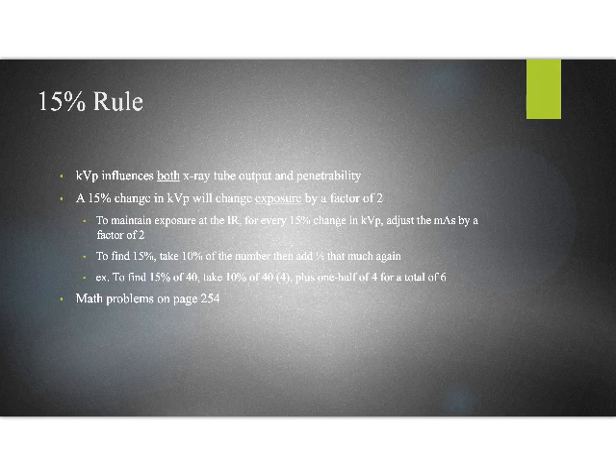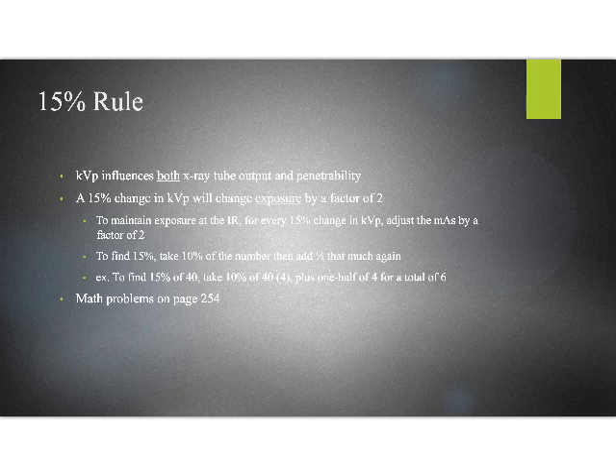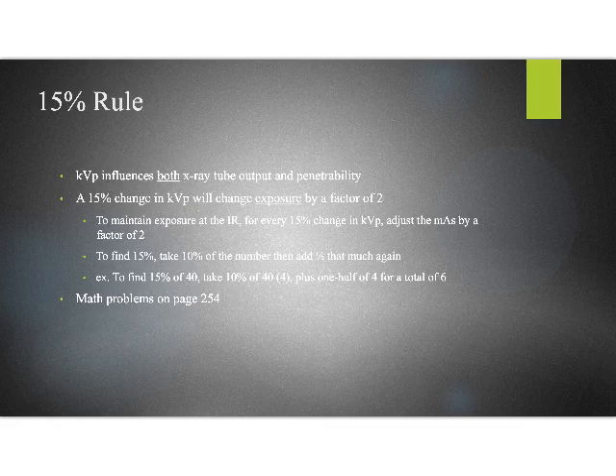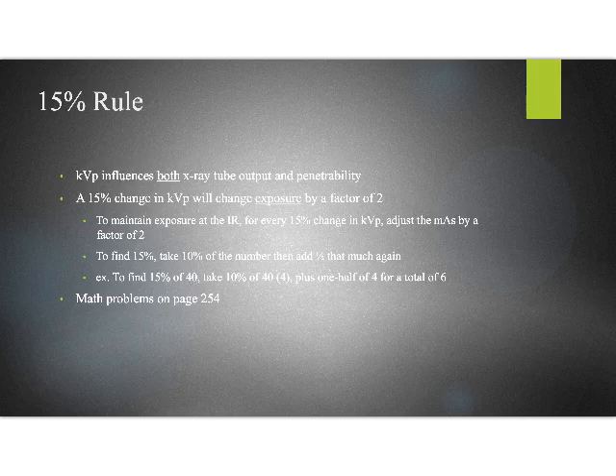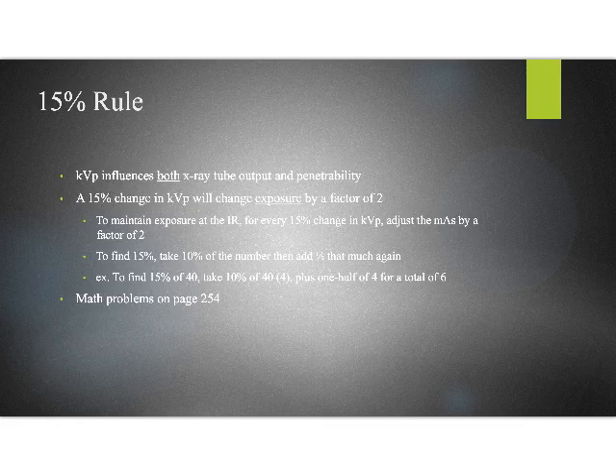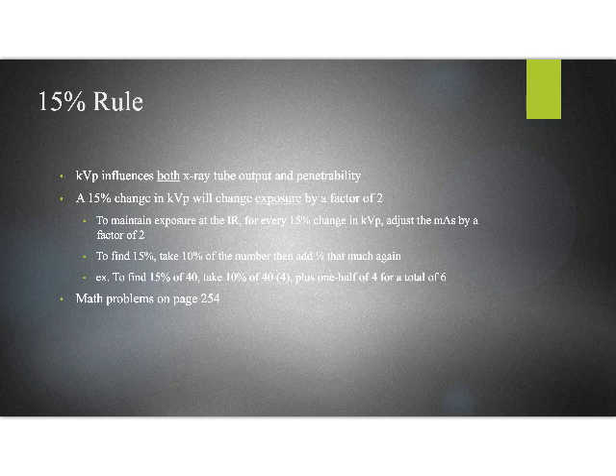All right. I'm going to change gears now. I'm going to talk about the 15% rule. Here's where stuff gets really muddy again. KVP doesn't just control quality. It also controls quantity. As we increase the potential difference across the x-ray tube, we're sucking more electrons across the x-ray tube. So we're also increasing the quantity of x-rays that are being produced. So mAs just controls quantity. KVP controls both quality and quantity. We're going to say it's primarily the way that we control quality, but it also does control quantity, at least the amount that passes through the patient.